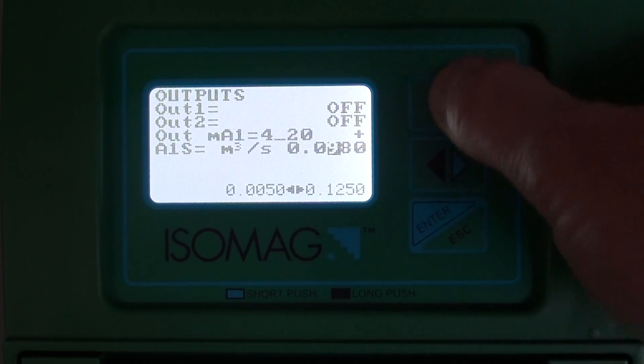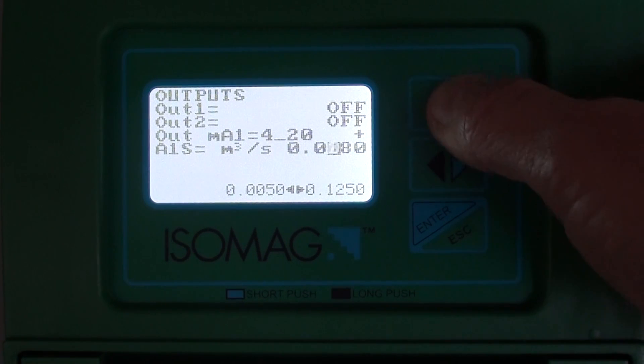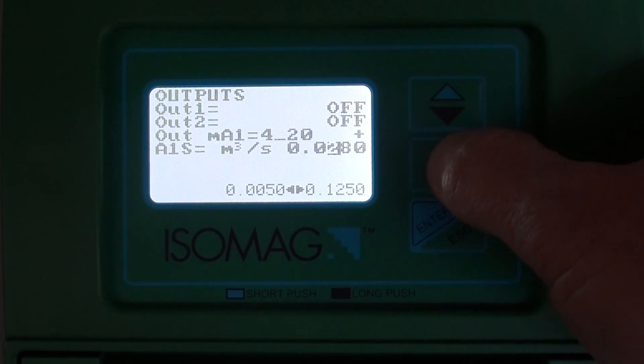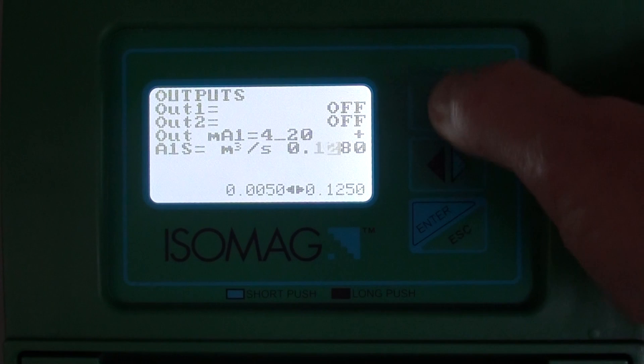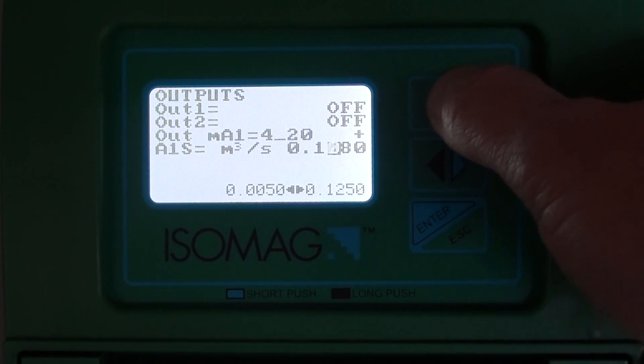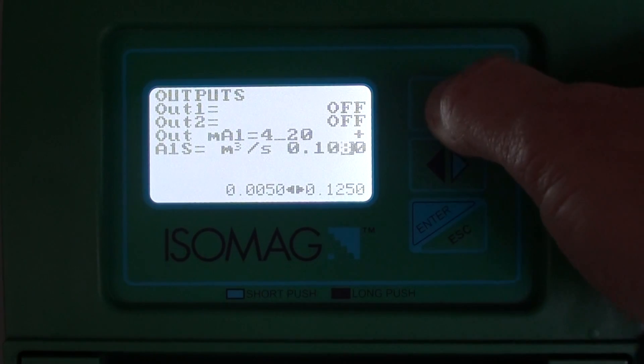As standard, the flow meter comes from the factory with a 20 milliamp equal to 3 meters per second flow velocity.